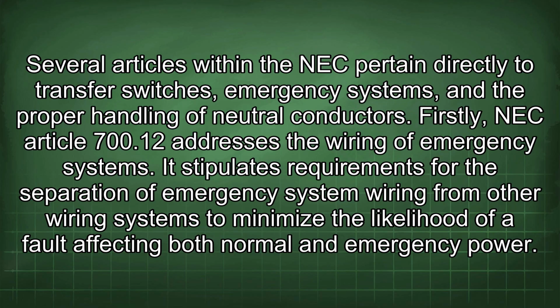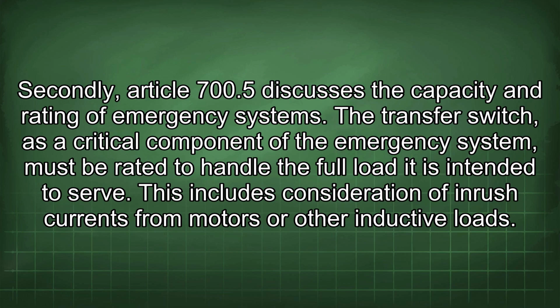Several articles within the NEC pertain directly to transfer switches, emergency systems, and the proper handling of neutral conductors. Firstly, NEC Article 700.12 addresses the wiring of emergency systems. It stipulates requirements for the separation of emergency system wiring from other wiring systems to minimize the likelihood of a fault affecting both normal and emergency power. Secondly, Article 700.5 discusses the capacity and rating of emergency systems. The transfer switch, as a critical component of the emergency system, must be rated to handle the full load it is intended to serve. This includes consideration of inrush currents from motors or other inductive loads.